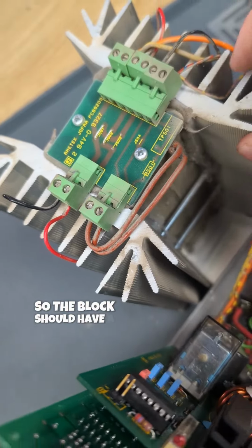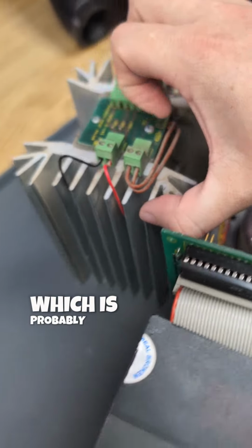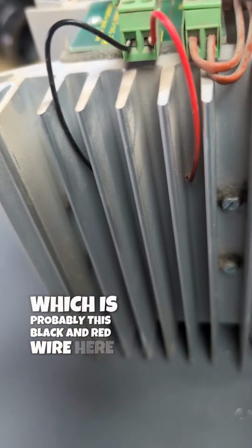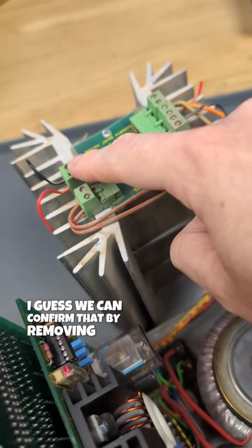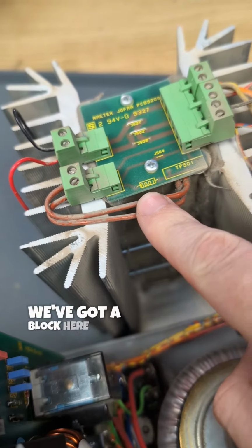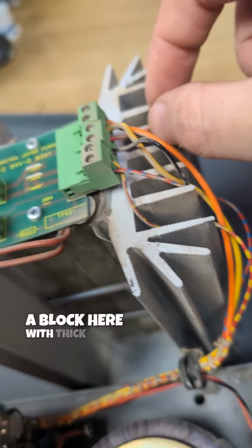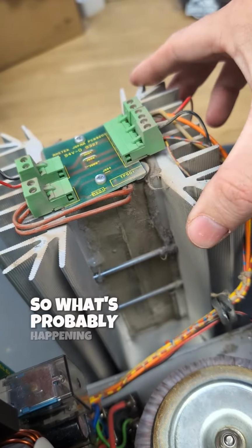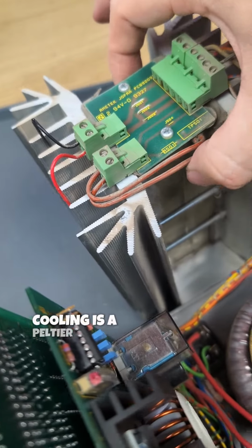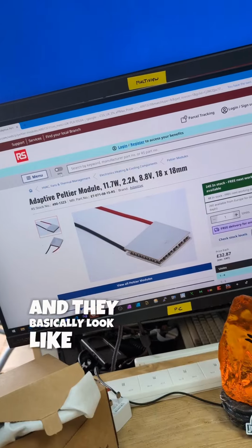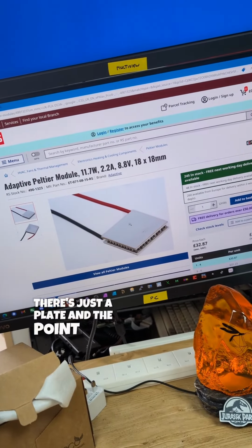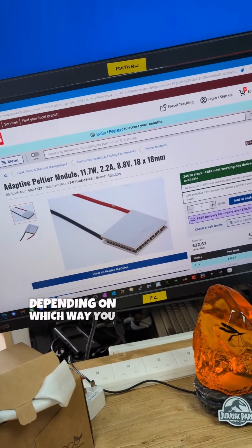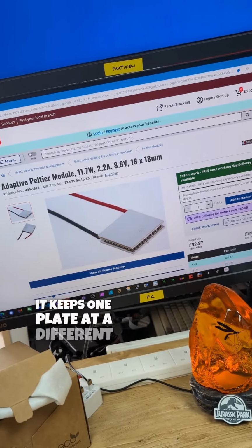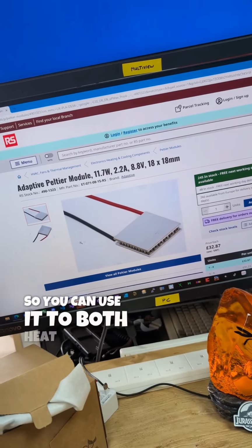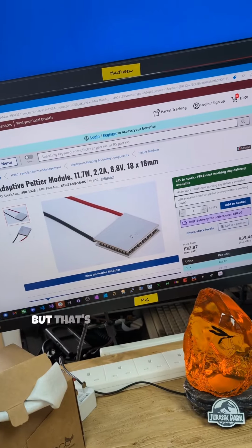So the block should have a temperature sensor, which is probably this black and red wire here. I guess we can confirm that by removing the wires and seeing the temperature gauge go different or wrong. We've got a block here with thick wires, a block here with thick wires. So what's probably happening for the heating and cooling is a Peltier sensor. And they basically look like this. There's just a plate, and the point of a Peltier is, depending on which way you apply the voltage, it keeps one plate at a different temperature than the other. So you can use it to both heat and cool. They're not very efficient, but that's how they operate.